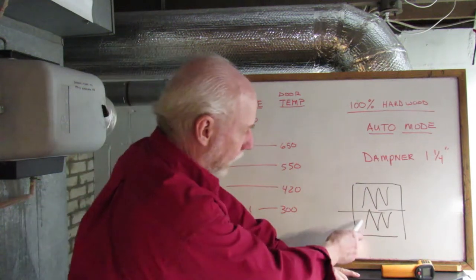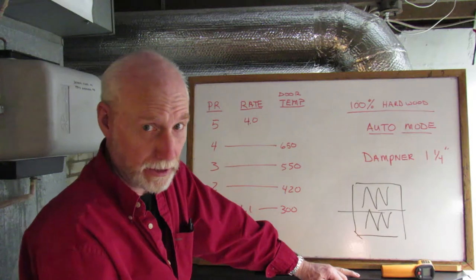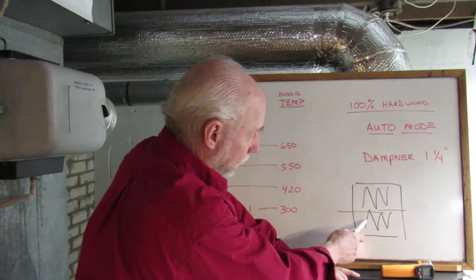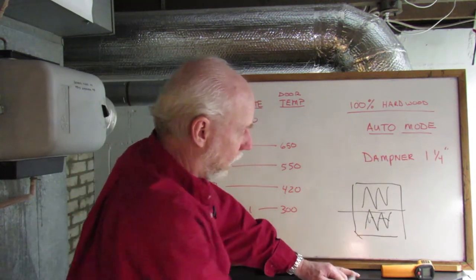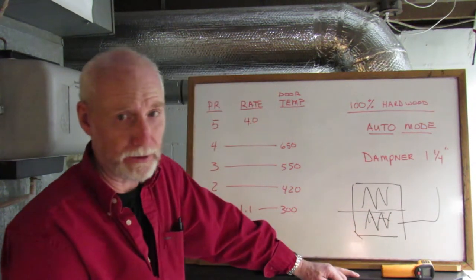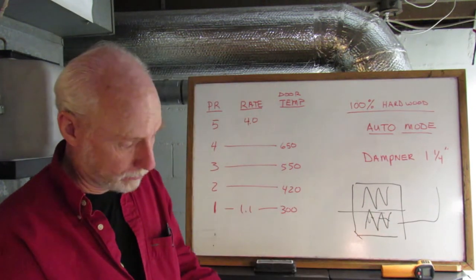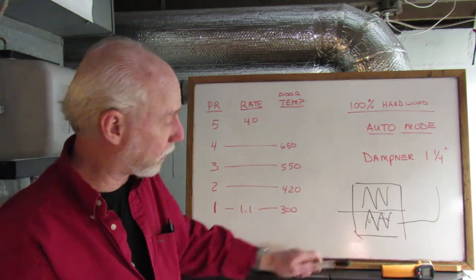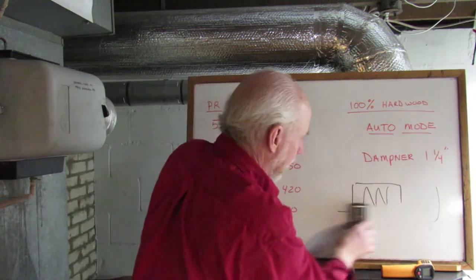If you end up putting too much air in there, you're going to keep your flames down low and all of your heat is going to go right out the stack. Make sure you've got that set up right and you'll burn a lot less fuel and get a lot more heat.